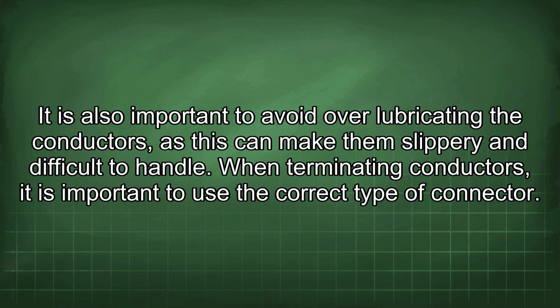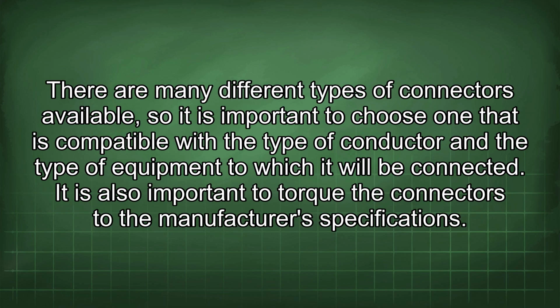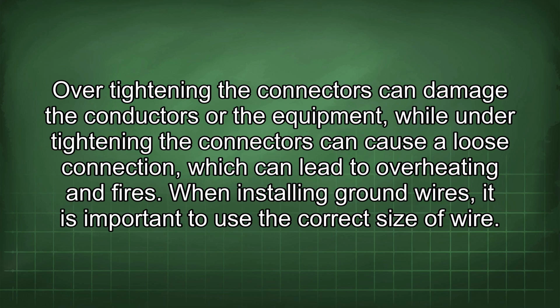When terminating conductors, it is important to use the correct type of connector. There are many different types of connectors available, so it is important to choose one that is compatible with the type of conductor and the type of equipment to which it will be connected. It is also important to torque the connectors to the manufacturer's specifications. Over-tightening the connectors can damage the conductors or the equipment, while under-tightening the connectors can cause a loose connection, which can lead to overheating and fires.